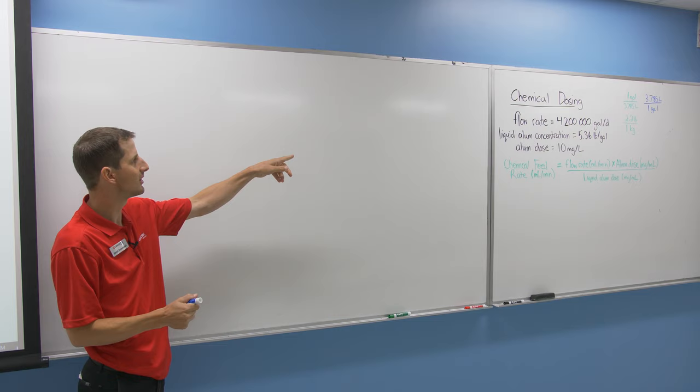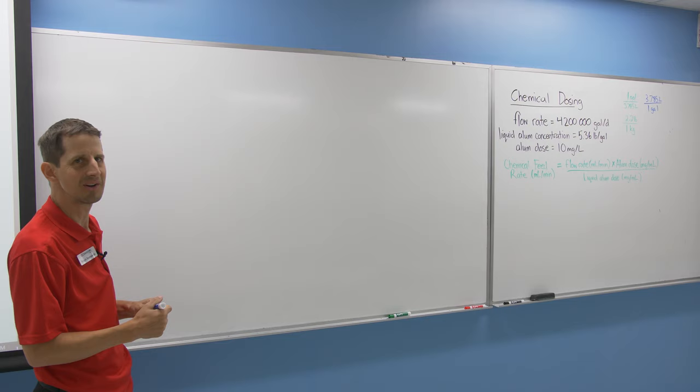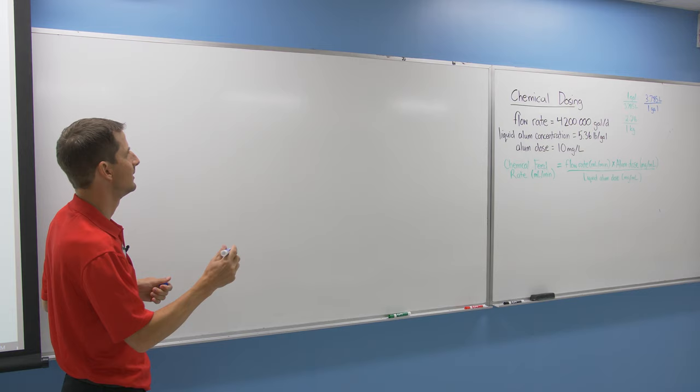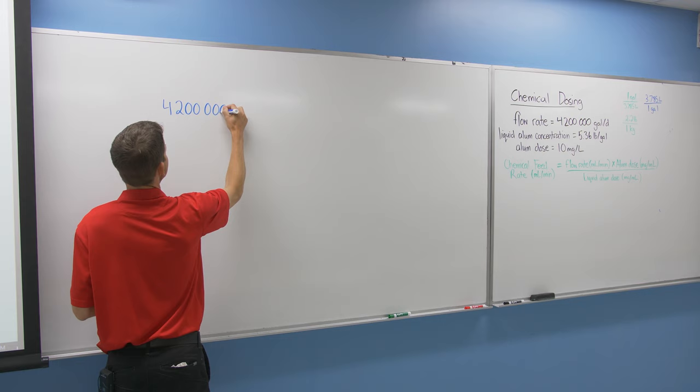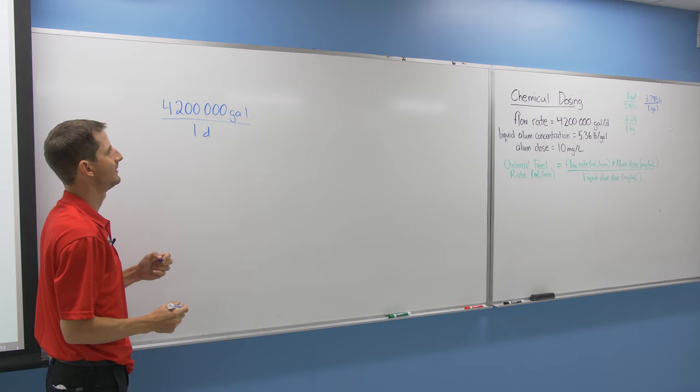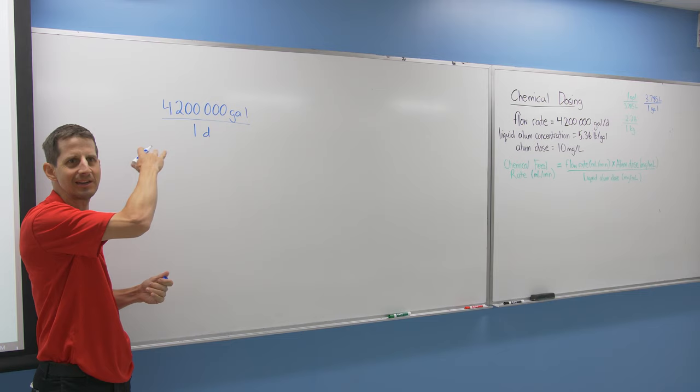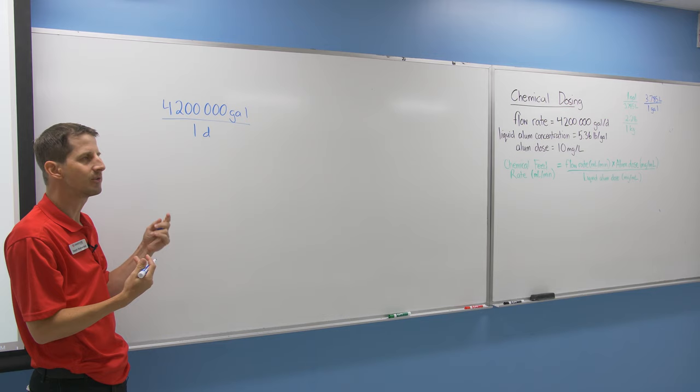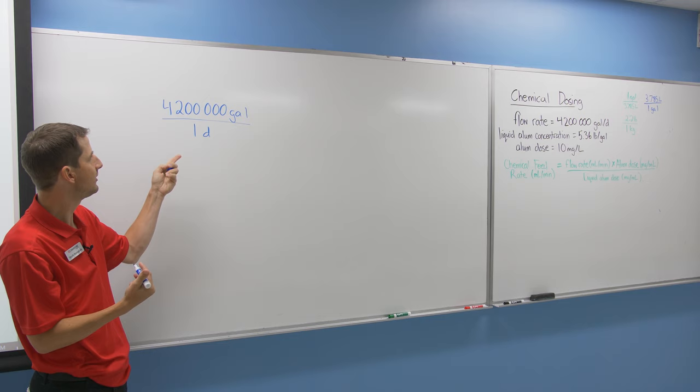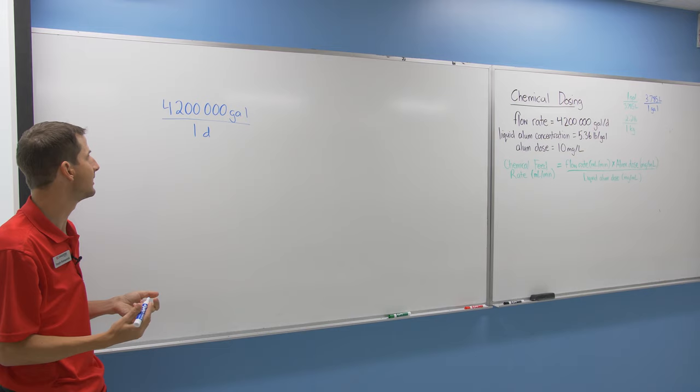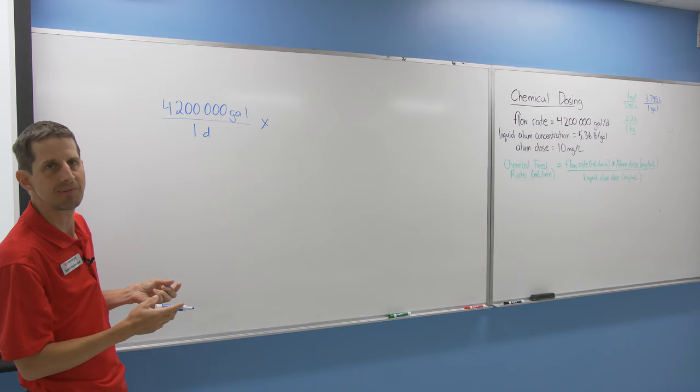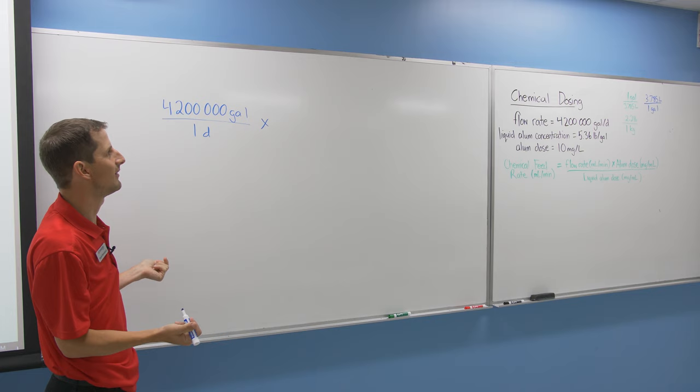The first conversion we need is the flow rate of 4.2 million gallons per day to milliliters per minute. So we're changing from imperial to metric and within the metric system. I'll write 4,200,000 gallons over 1 day. Now we need conversion factors. We have 3.785 liters in a gallon. The trick is: where do I put the 3.785, on top or bottom? For unit conversions to work, we need to cancel units. Gallons is on top, so the other gallons has to be on the bottom.